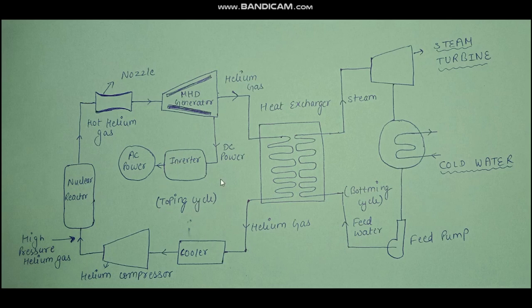This is the whole diagram of the closed cycle seeded inert gas energy system. I will explain its working step by step. The helium gas is seeded with cesium and heated to very high temperature in a nuclear reactor. The hot helium gas is then passed through a nozzle so that its velocity increases, and this gas is supplied into the MHD duct, where it produces DC power.